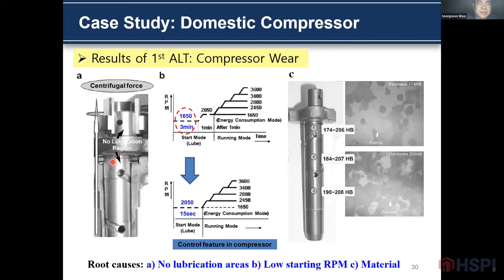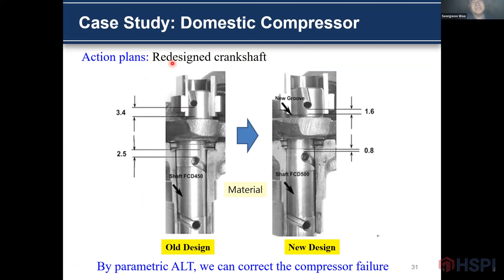We checked the design of the compressor and found three design problems: one is a low lubrication area, another is a low starting RPM, and the third is the crankshaft material. As an action plan, we redesigned the compressor, changing some dimensions, adding some oil groove, and changing the crankshaft material from FCD 450 to FCD 500. By parametric ALT, we can correct the compressor failure.